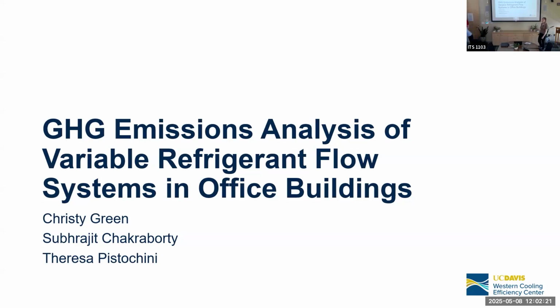Well, I guess I'll start the presentation since we've got some people online. I'm Christy Green. I'm a research engineer at the Western Cooling Efficiency Center at UC Davis, across the street. I'm going to be presenting on an analysis we did of GHG emissions in variable refrigerant flow systems in office buildings. The importance of this is that a lot of times when you think about decarbonization, you might look at just the on-site emissions or on-site energy use associated with installing a particular technology. But in this case, we're going to look at the emissions all the way from the production of either energy or natural gas up to the point of end use. We're doing that with the VRF system, and we're going to compare it to a baseline packaged rooftop unit with VAV boxes that's usually used in commercial building space conditioning.